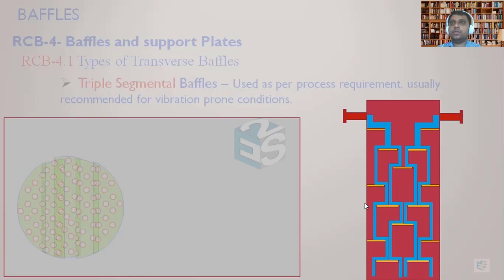So wherever you don't have very high velocities, rather where you want to have a very smooth flow which will come in contact with the tubes and should pass very slowly, there also this type of arrangement will be preferred in case of falling film arrangement so that the fluid coming at very slow velocity and the outside fluid will also go by touching the tubes very smoothly. So this type of arrangement would help.